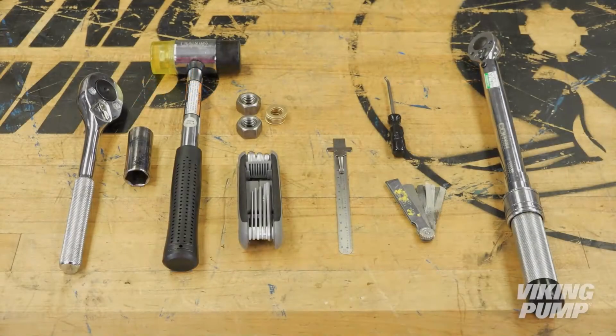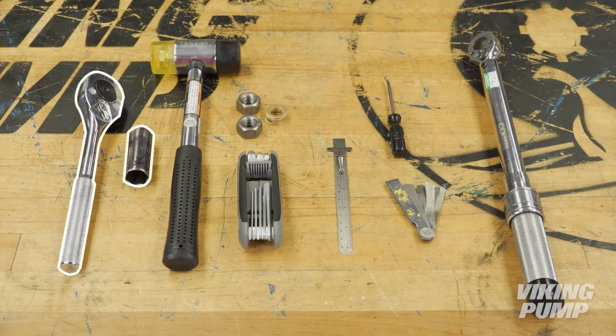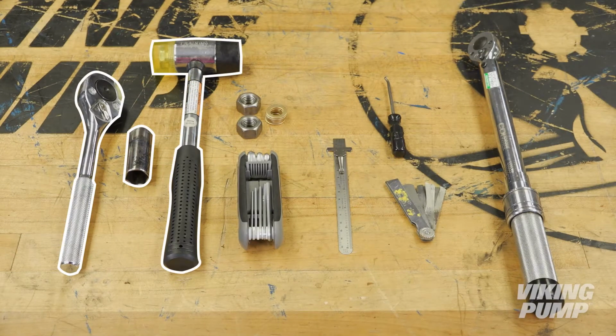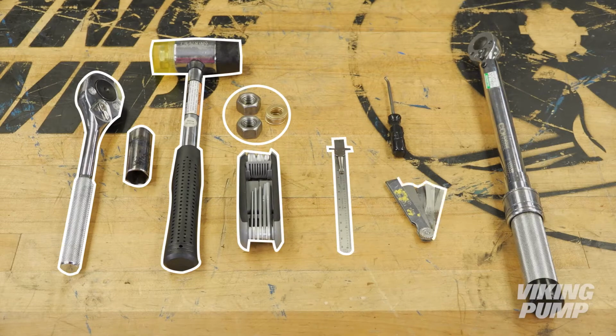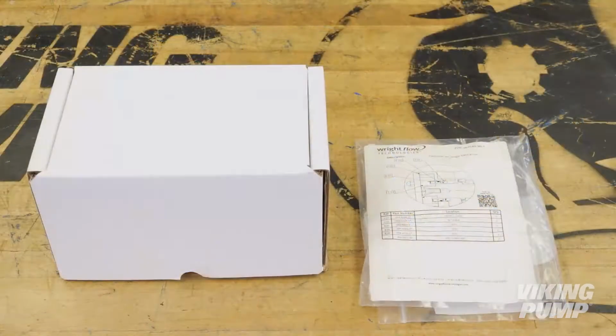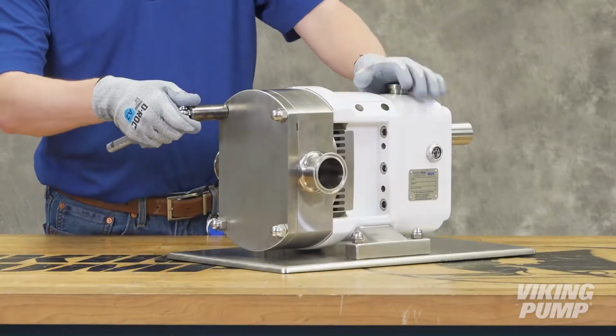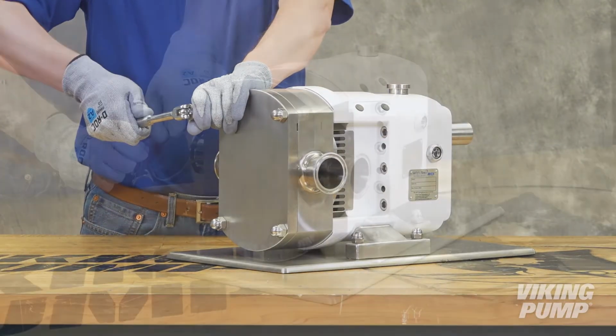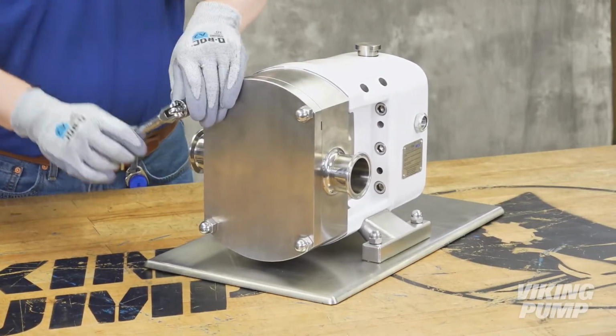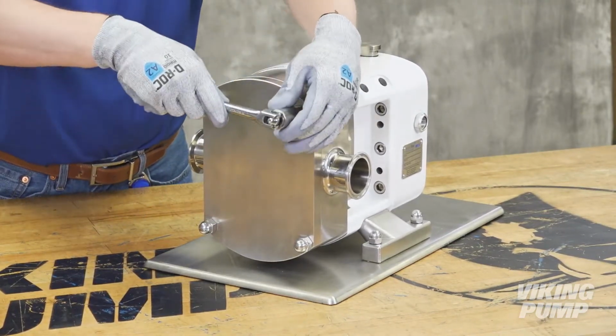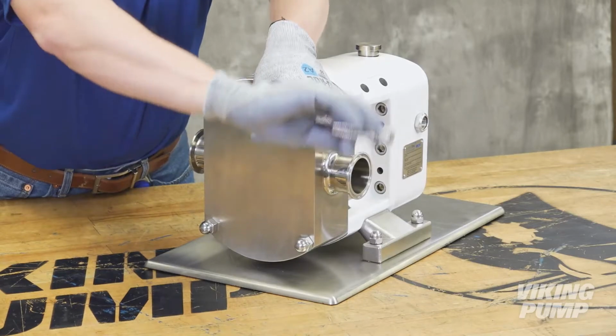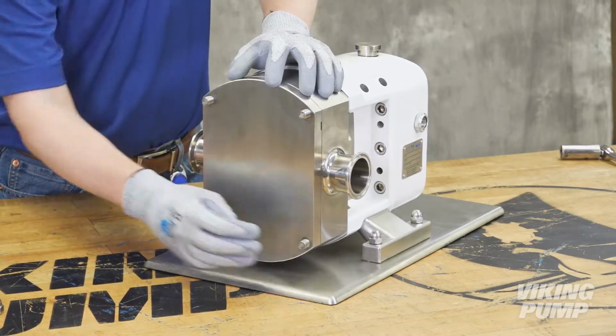The following tools are required: ratchet and socket set, soft-headed hammer, spacers, Allen wrenches, ruler, feeler gauges, O-ring pick, and a torque wrench. Each Viking Pump seal kit and elastomer kit contain all required spare parts. To begin, loosen and remove the pump cover dome nuts. Note that on CP10 size pumps, removing the dome nuts will also loosen the rotor case. Take care not to rotate the shaft after removing the dome nuts.